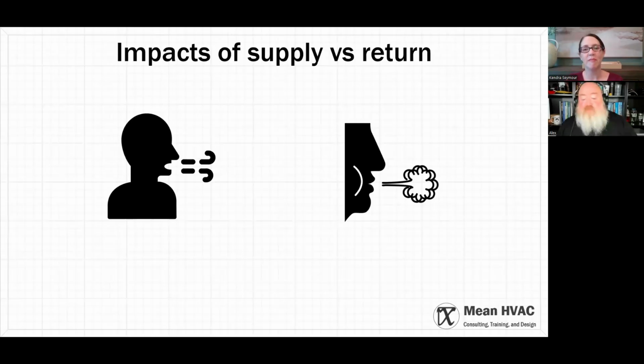Especially for those of you building high efficiency homes — if you read Manual T and tried to follow all of its advice, you would need a second blower that just moved air, ducted in such a way that it didn't mess with your first blower. I know somebody who did one — he called it the Franken duct system, and it is as expensive as it sounds and totally overkill, because we have good insulation. We just need a decent velocity from our grills, and we should be okay.